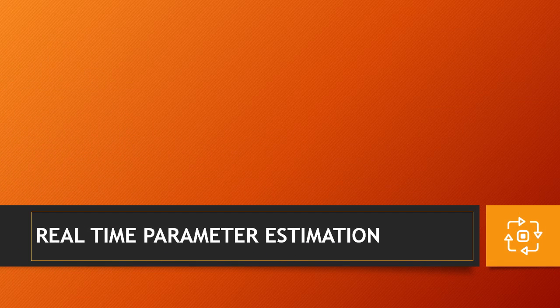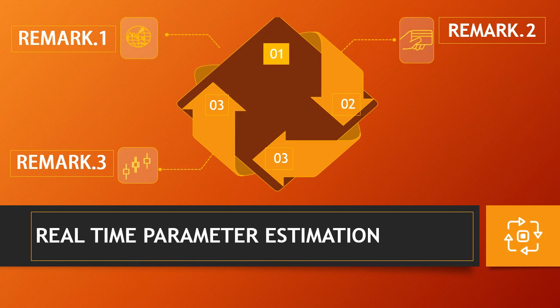In real-time parameter estimation, we have 4 remarks. Remark 1. We have used the phrase generator rotor angles interchangeably with phasor measurements. What we intend is that when we have a phasor measurement unit located on the EHV or HV bus of a generating plant, we will have a suitable detailed model of the generator for simulation purposes, but also a classical generator model consisting of a voltage source behind transient reactance. The generator internal voltage in the classical model is easily computed from the terminal voltage and the current phasor measurements. And then remark 2.